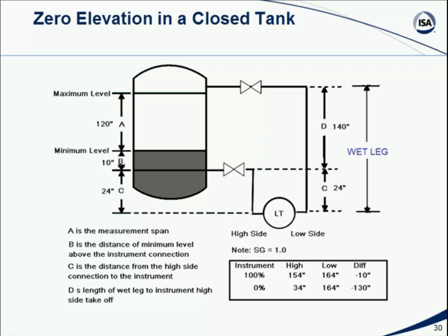So what we now have is a situation where actually things are reversed. On the transmitter here, the high side and low side actually switch, because now the pressure on what is now a wet leg is actually the high pressure, and what we're looking at is the difference between it and the level in the tank. So as the tank level goes up, the difference between the high side and low side goes down, not up, because the pressures are getting closer to each other. Once the level in the tank is all the way up to the maximum level, the difference between the two sides is going to be just 10 inches of fluid pressure. So here we've got a case where the dry leg is no longer a dry leg, it becomes a wet leg. And we basically have to switch the transmitter around and think of what is now a wet leg as our high pressure side.